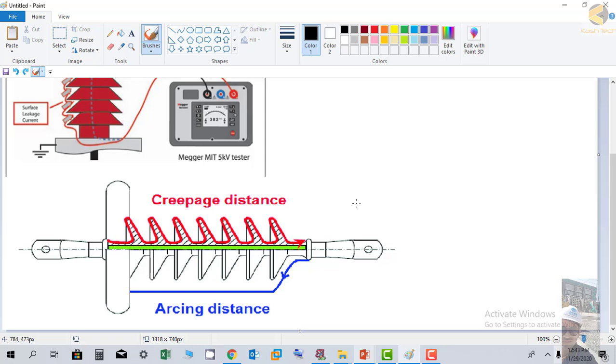If the bushing or insulator is not properly cleaned, the results will vary. We won't be able to compare results each time or analyze insulator deterioration over time, because the values depend on how well it's cleaned and the climatic conditions.